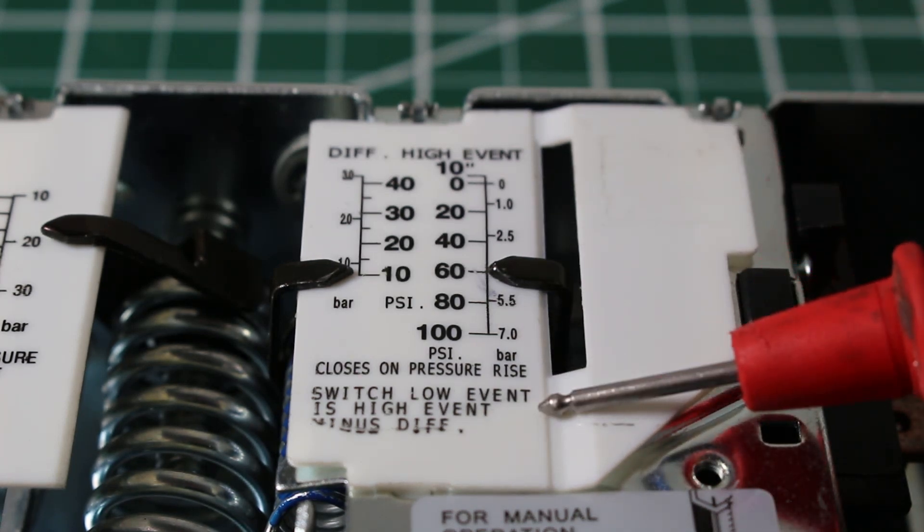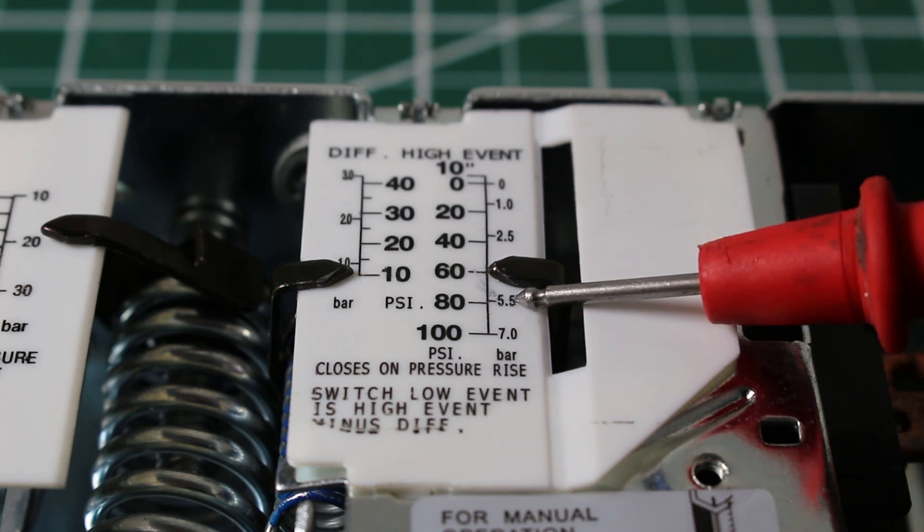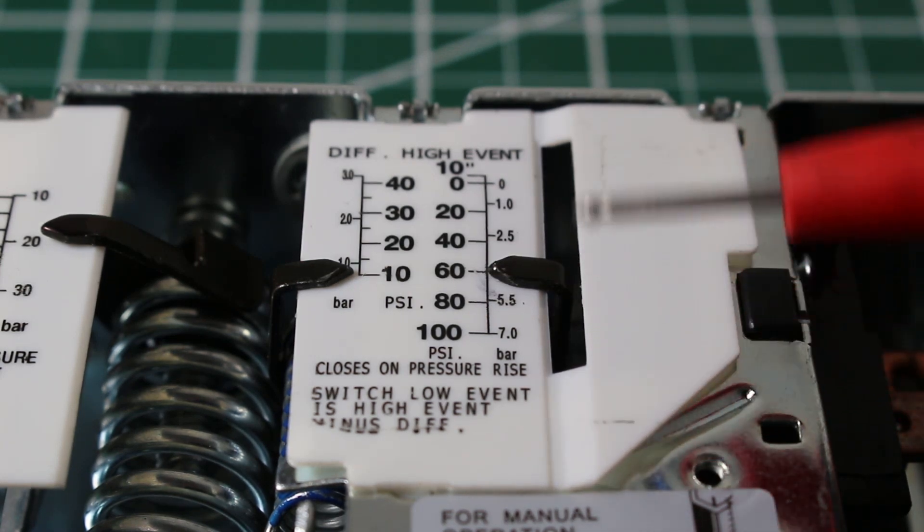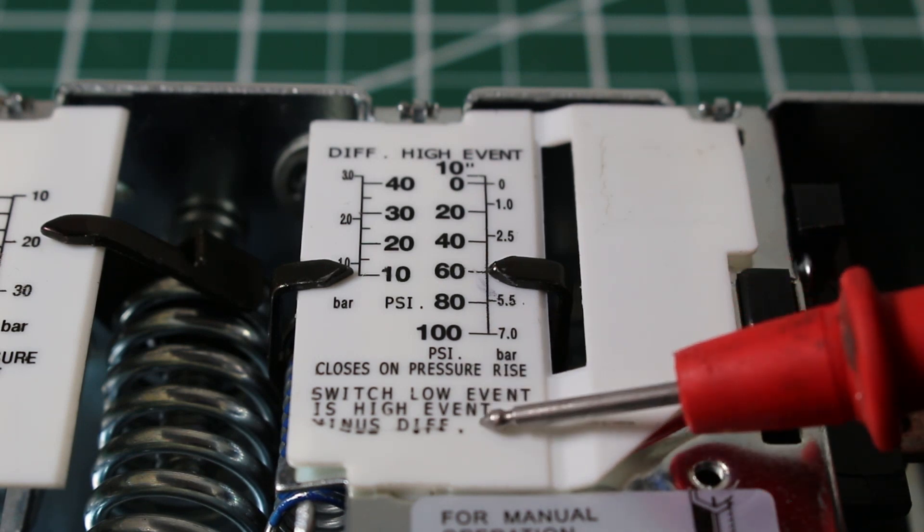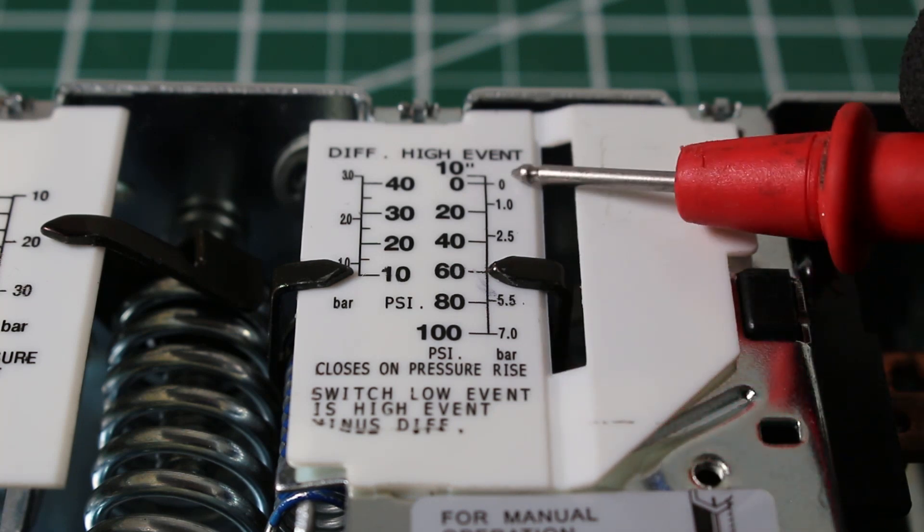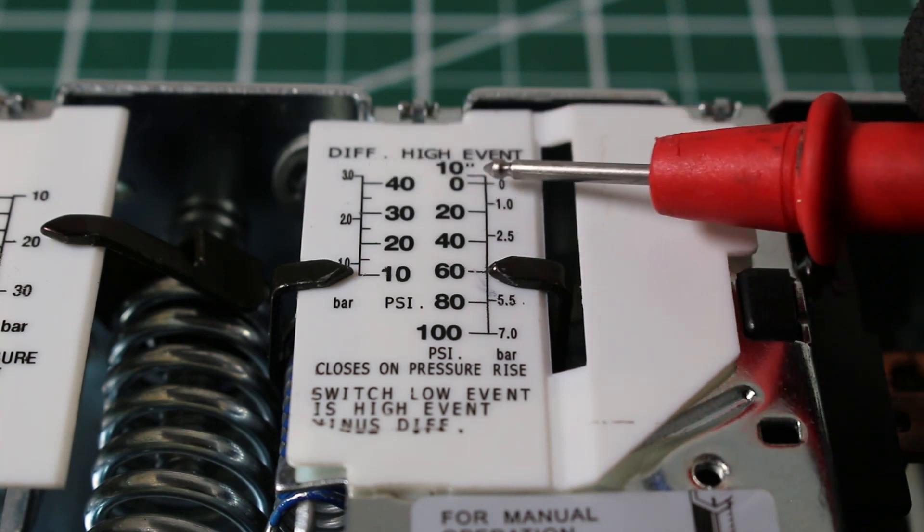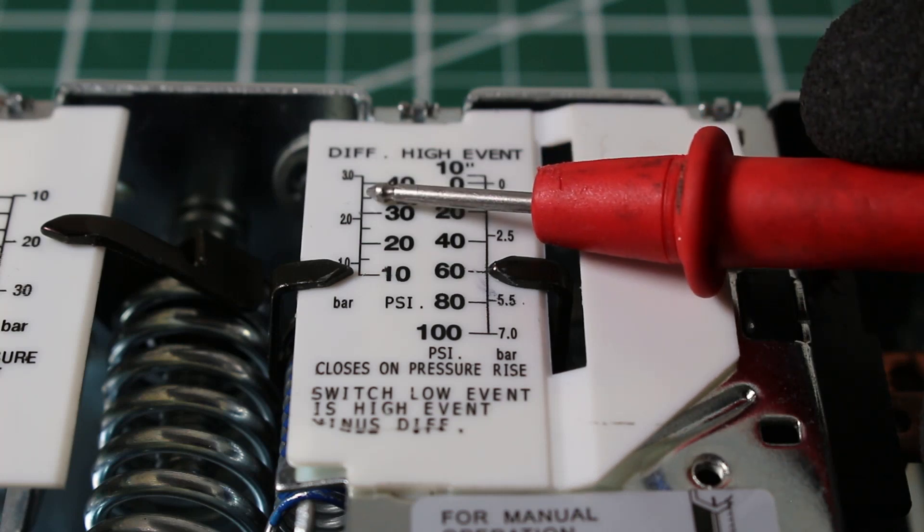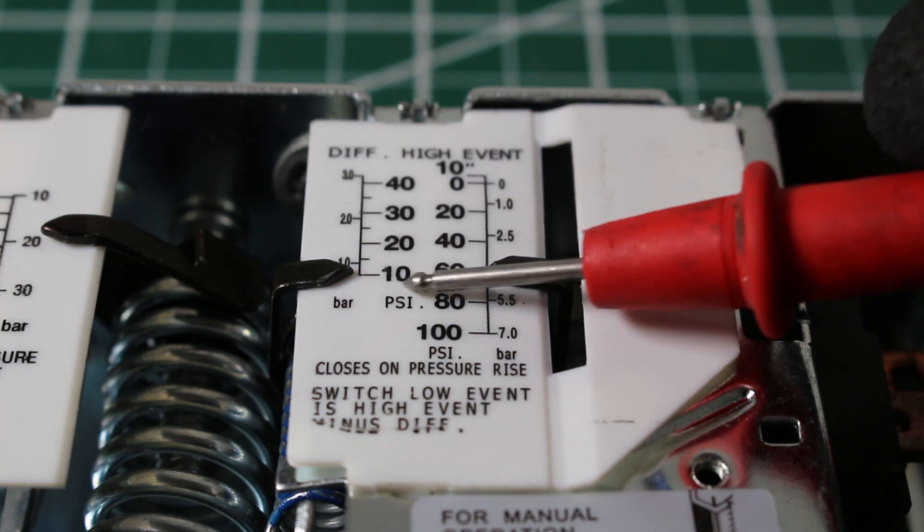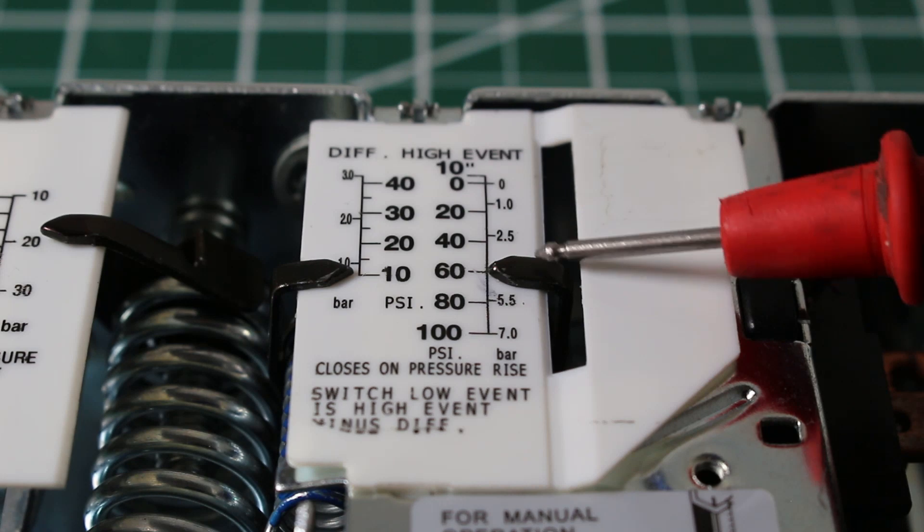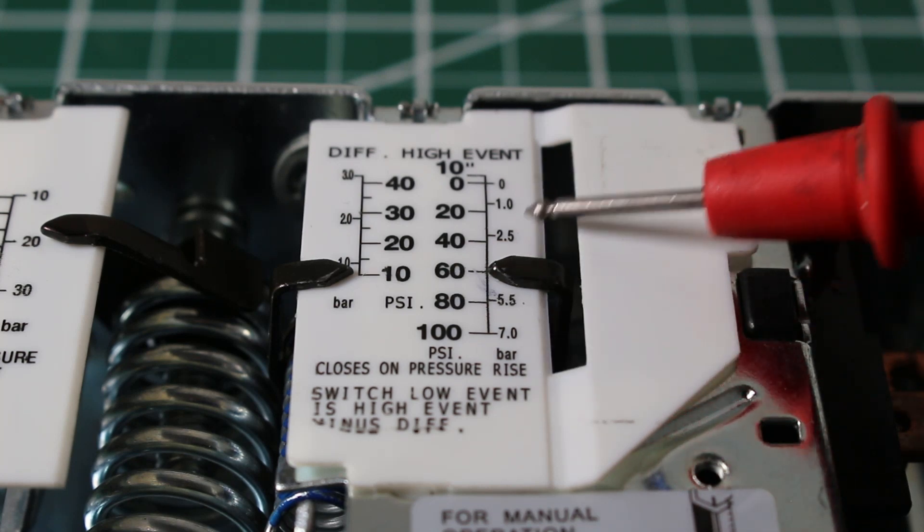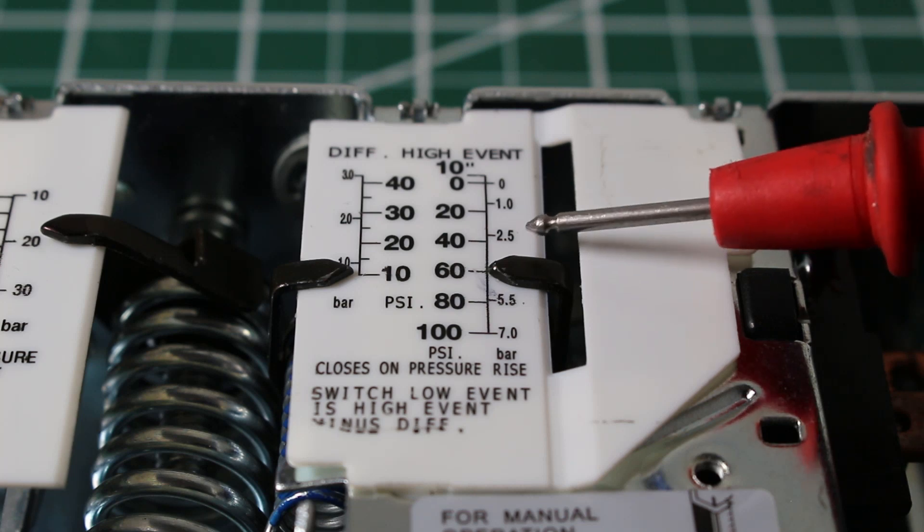So what is our low event? Our low event is the pressure we want our system to cut off at. Right now it is set to 50. I'll explain that, but let's go over what this means. So it says low event is high event minus differential. So the low pressure this control will be set at is going to be the difference between your high event and your differential, right? High event minus differential. So let's see what this is set at. So our high event is 60 and our differential is 10. That means our low event is 50. So at 50 pounds of pressure, this control will open our circuit and stop everything to protect it.